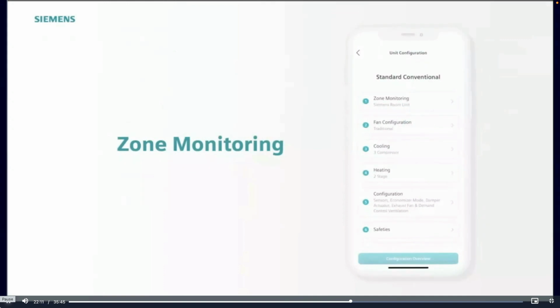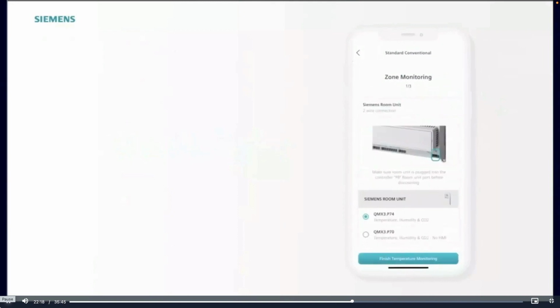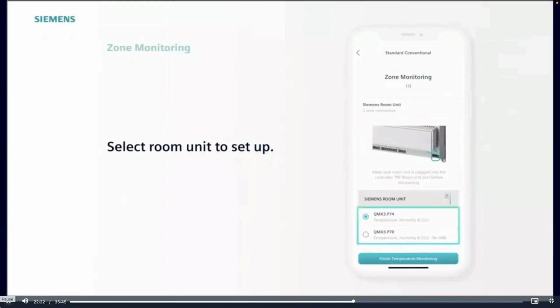From this point, you have step-by-step guidance to complete the configuration, starting with Step 1, Zone Monitoring. Here, you'll select which room unit is being set up. The QMX3.P74 and QMX3.P70 both have temperature, humidity, and carbon dioxide sensing. However, the P70 does not have a display, indicated as no HMI.